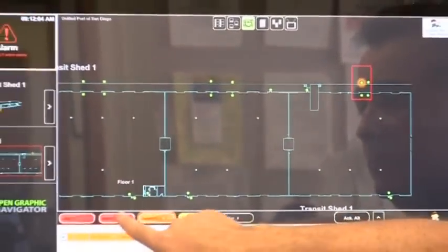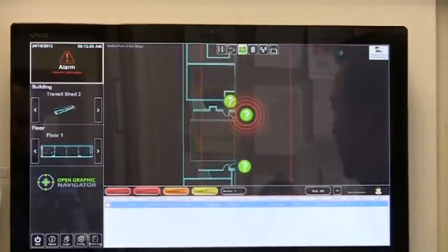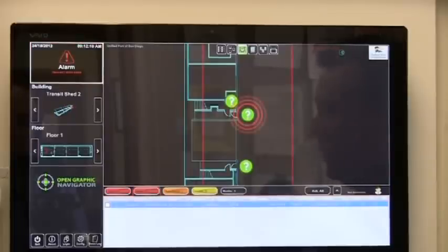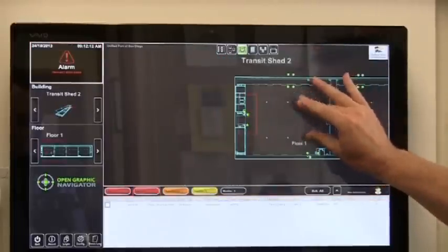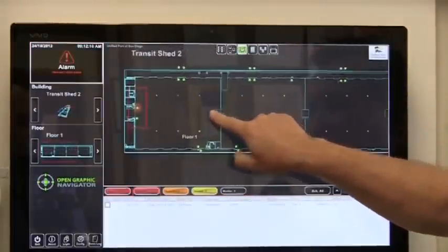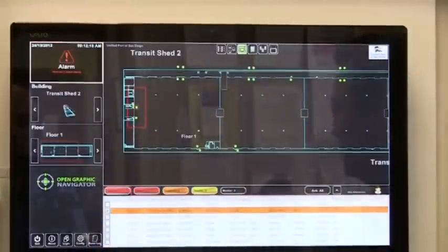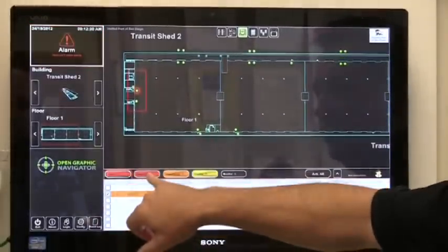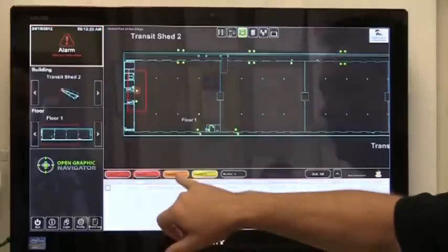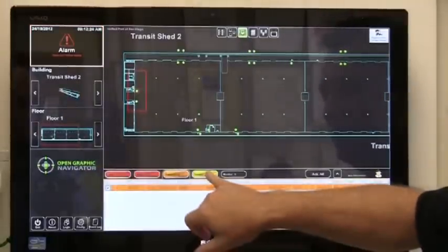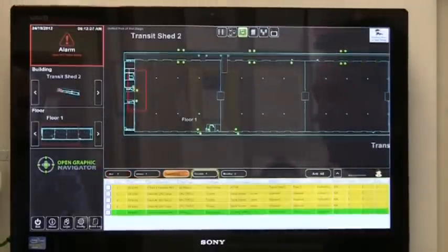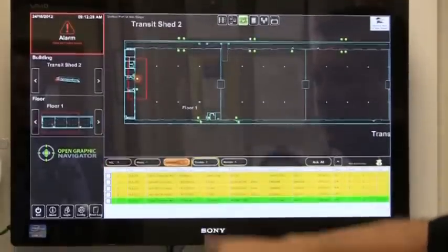We can see that multiple events are accessible. Going back to the alarm and double tapping will bring us to the alarm event again. Multiple events show up in the system: all events are shown unfiltered, alarm events filtered, and supervisory events filtered. The trouble events — which are the signal silence that occur on the system — show in the trouble menus.